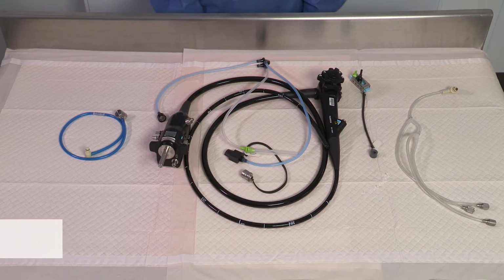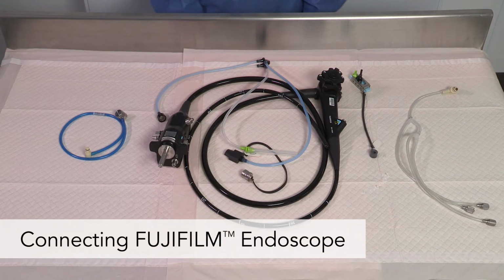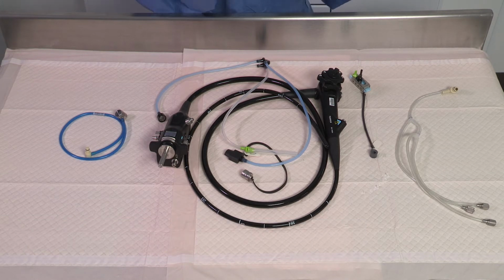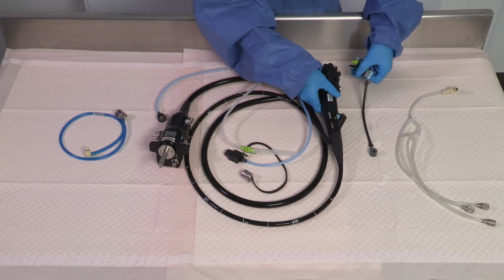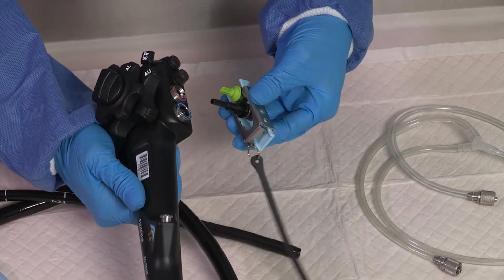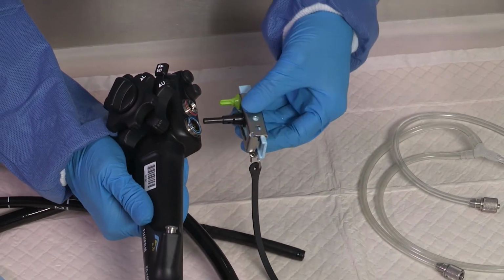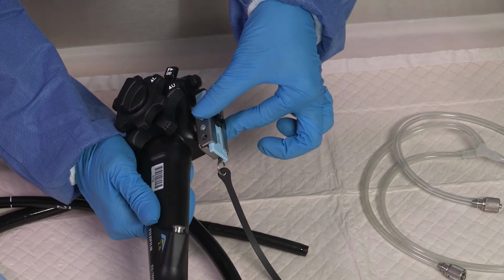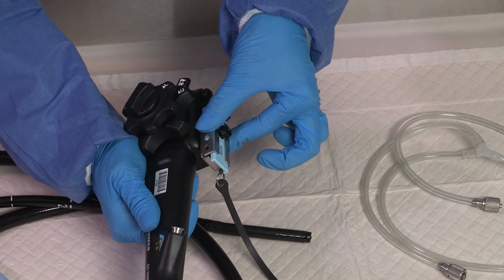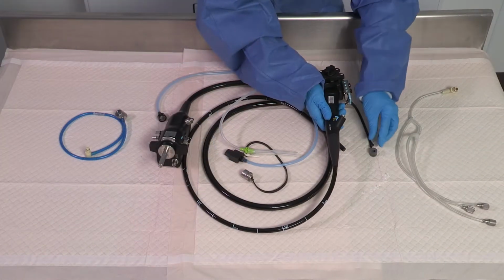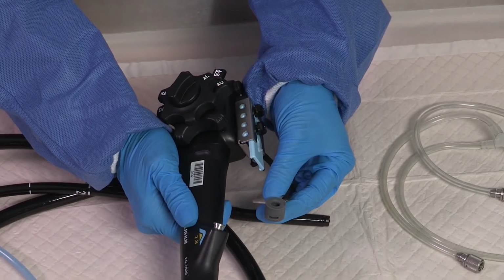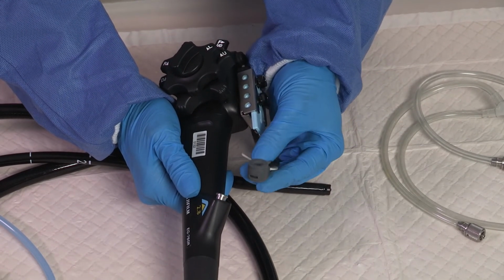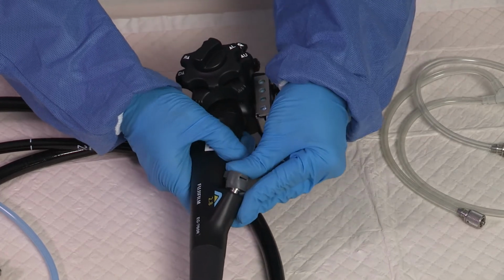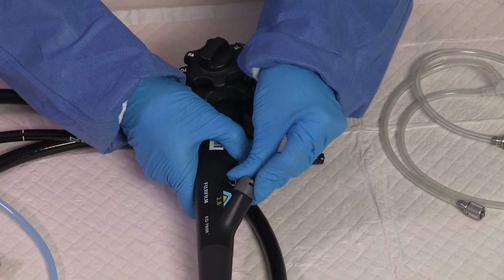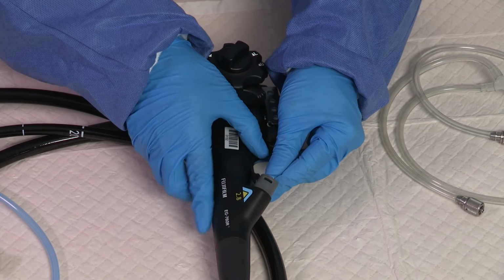This segment will demonstrate how to connect a Fujifilm 700 series endoscope to the DSD EDGE Reprocessor. Using the Fujifilm cylinder adapter, insert the air, water, and suction plugs into the air, water, and suction valve cylinders of the endoscope. Push the frame down and then slide forward. Align the rubber instrument channel inlet cap over the instrument channel inlet of the endoscope. Push down and over the inlet until fully engaged.